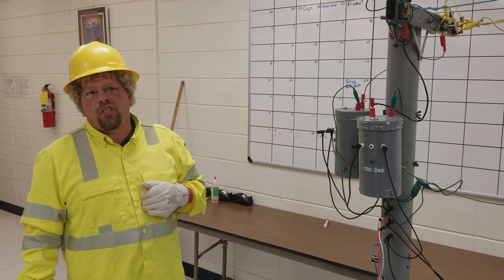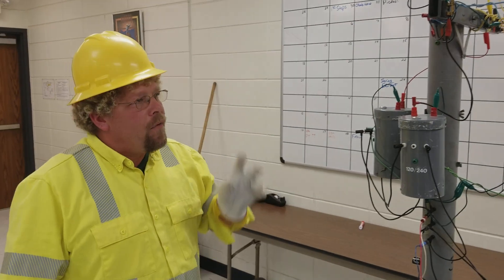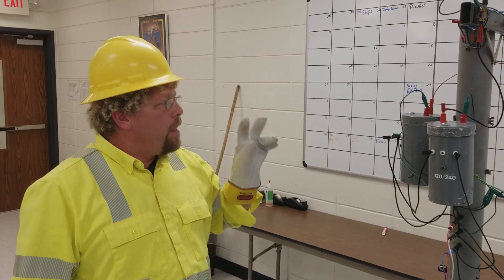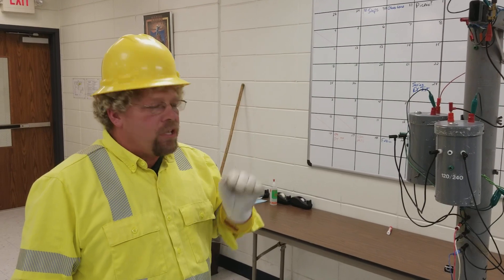So to answer the question, you can absolutely phase two banks. One fed from A and B. The other one fed from B and C. You can successfully parallel them. Thank you very much.